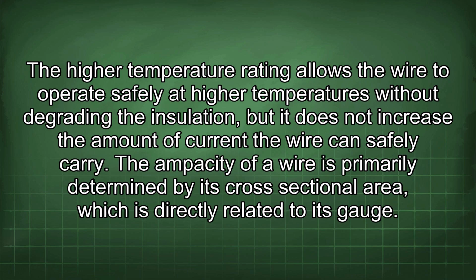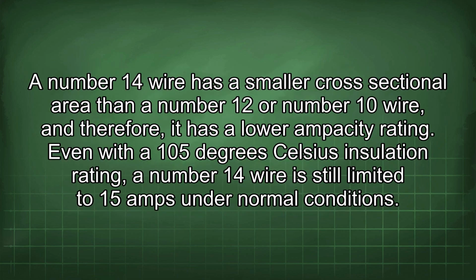The ampacity of a wire is primarily determined by its cross-sectional area, which is directly related to its gauge. A number 14 wire has a smaller cross-sectional area than a number 12 or number 10 wire, and therefore it has a lower ampacity rating. Even with a 105 degrees Celsius insulation rating, a number 14 wire is still limited to 15 amps under normal conditions.